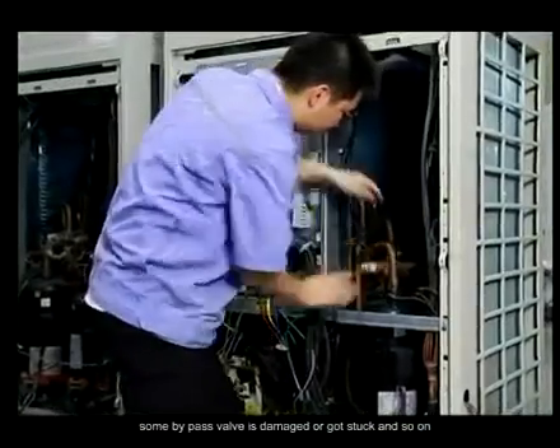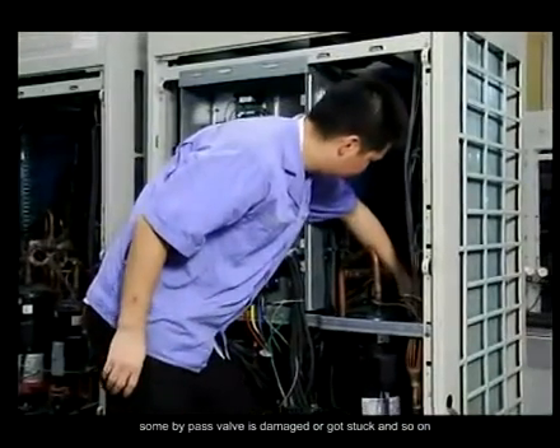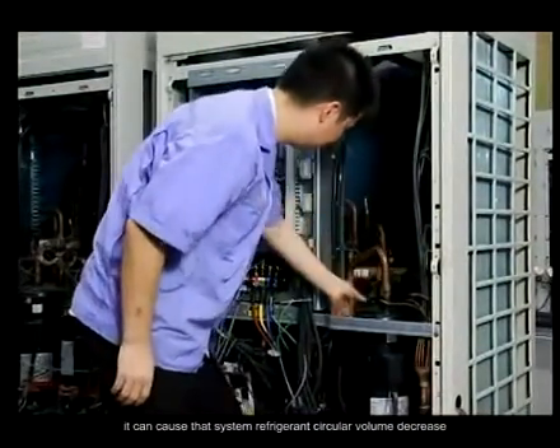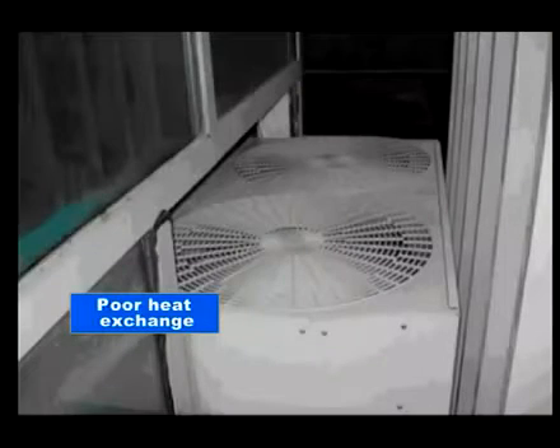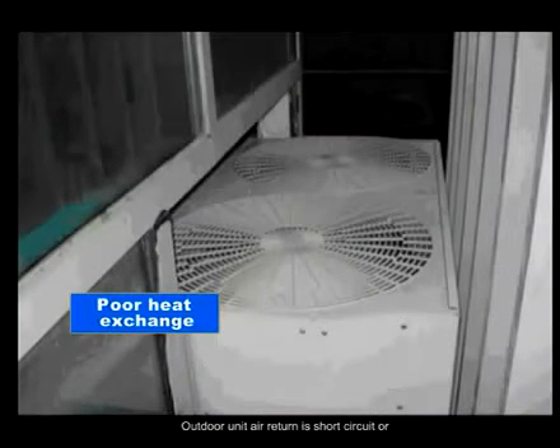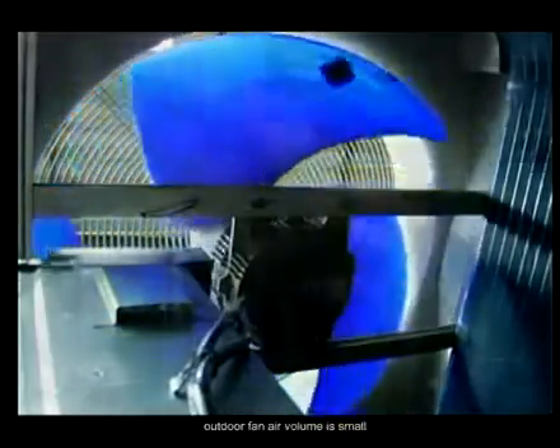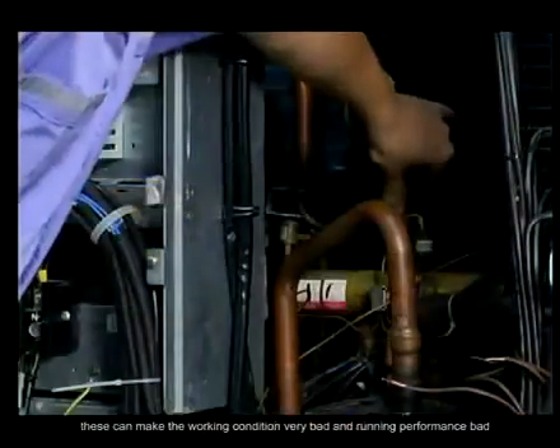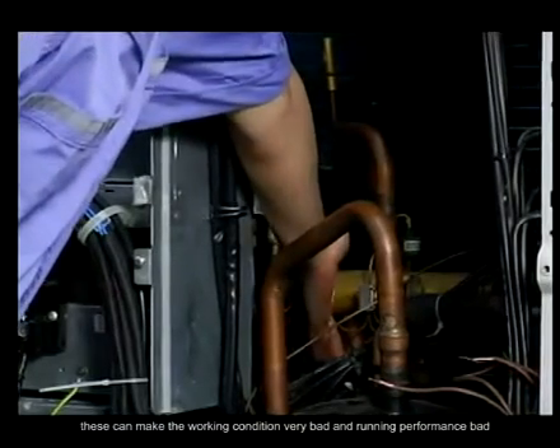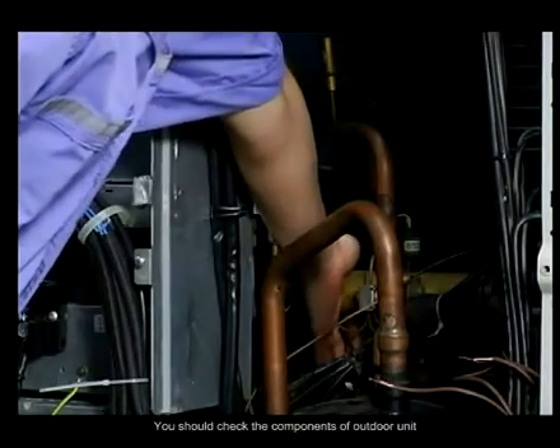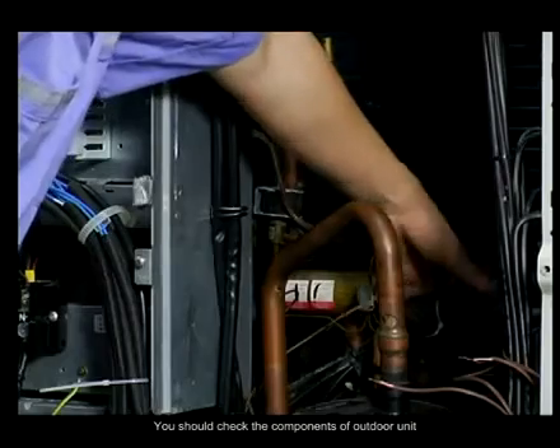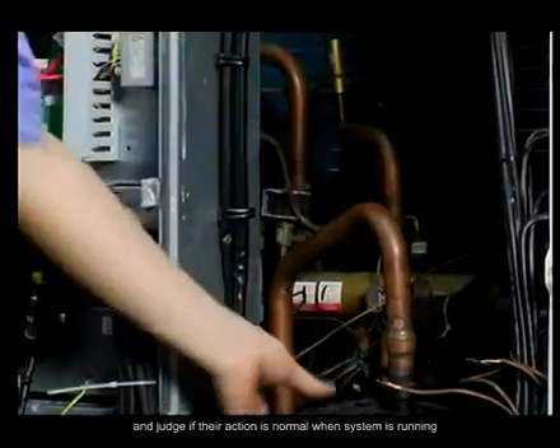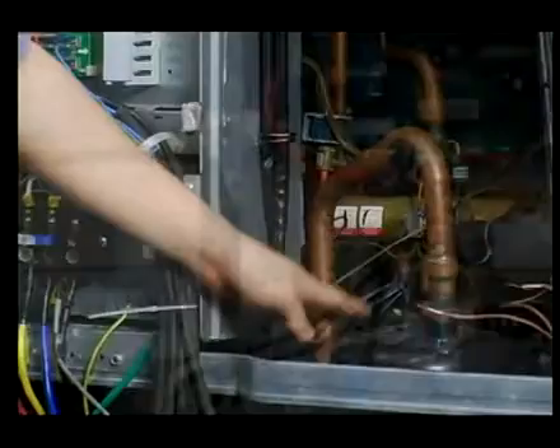Some bypass valve is damaged or got stuck, and so on. It can cause the system refrigerant circulation volume to decrease. The outdoor unit air return is short-circuited, or the installation environment is not good for heat exchange. Outdoor fan air volume is small. These can make the working condition very bad and running performance bad. You should check the components of the outdoor unit and judge if their action is normal when the system is running.